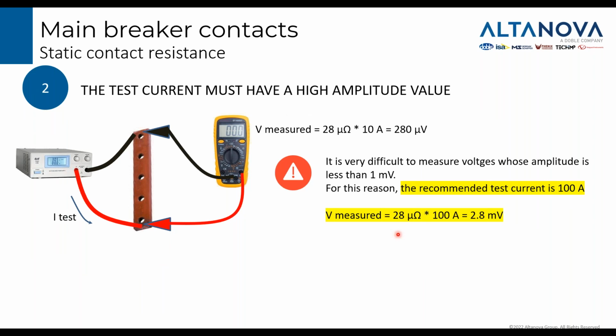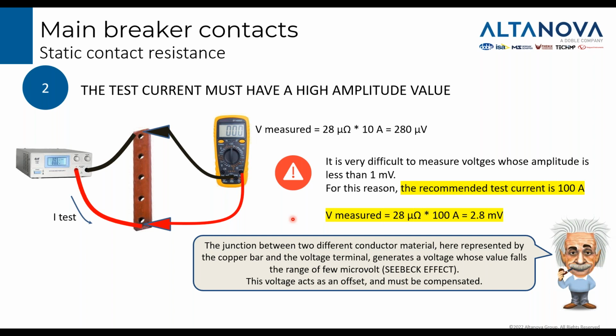The test current must have a high amplitude value. As I said before, if I generate a very low value, let's say 10 amp, I have to measure voltages in the range of microvolts. So it is recommended to test the static resistance with at least 100 amp. So the voltage can reach 2.8 millivolt. But even if you cannot generate such high current, but you trust a lot in your multimeter that can measure the voltage with extremely high accuracy, you have to remember that there is one aspect, the so-called Seebeck effect.